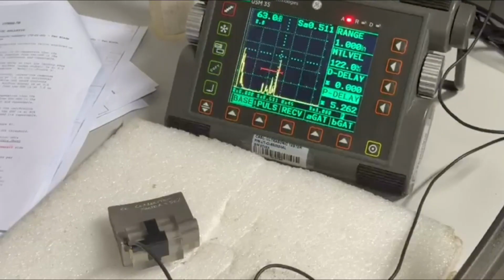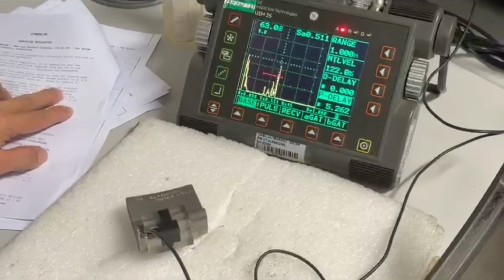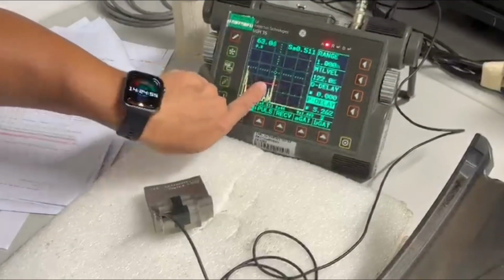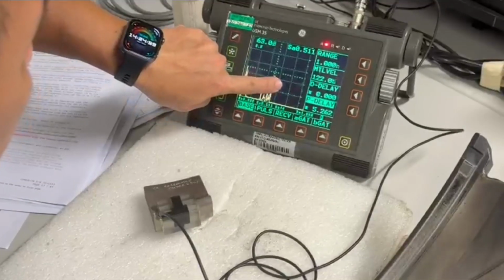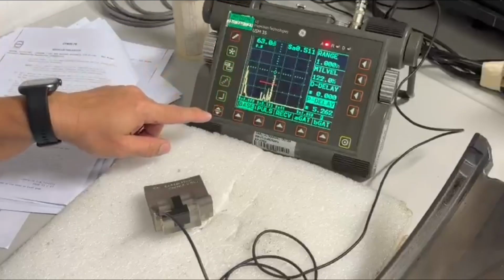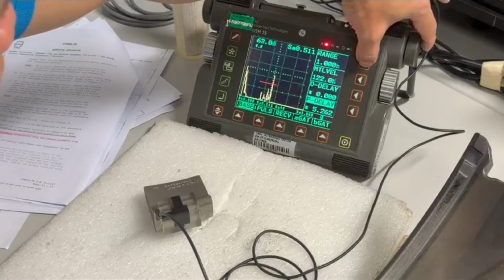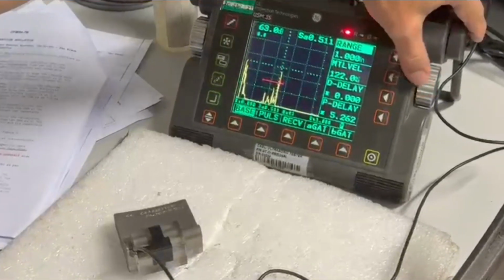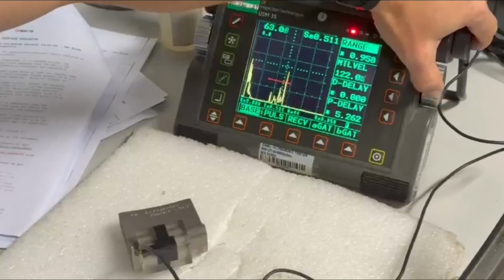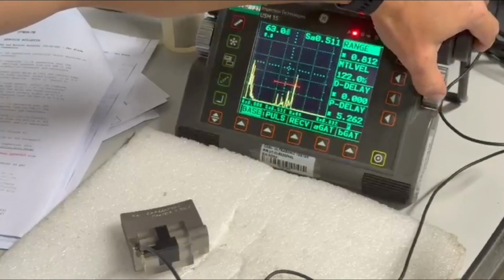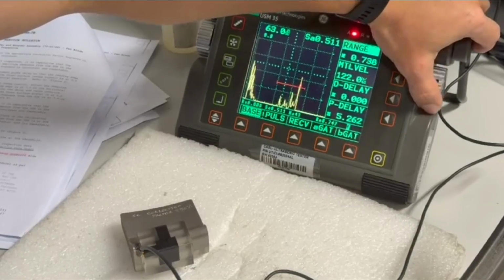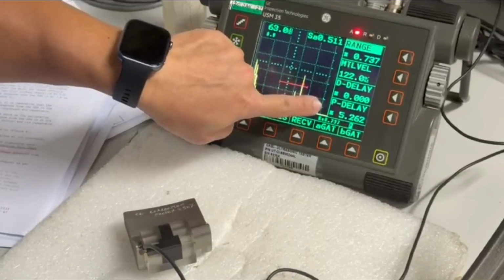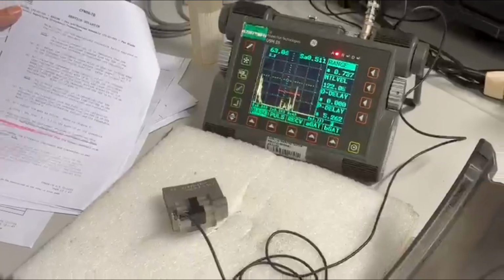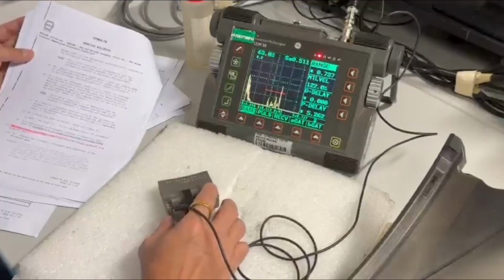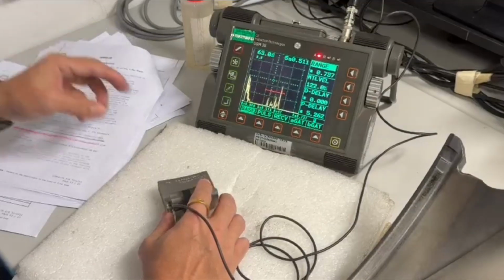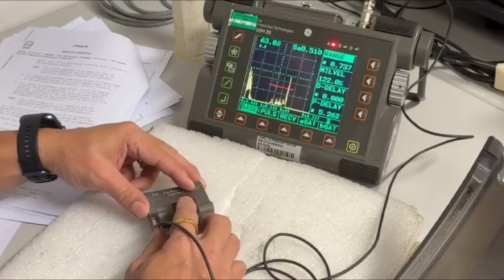Then, using the instrument range control, adjust the response from the side drill hole so that the trailing edge is at 7. So this, our side drill hole signal, we're going to move that to the 7th here. So to do that, we need to adjust the range, measure range. Set to 7. That's it. 7, 8, 9 in between, then 10. Okay, we try to scan back and forth. Okay, still managed to get the 50%.